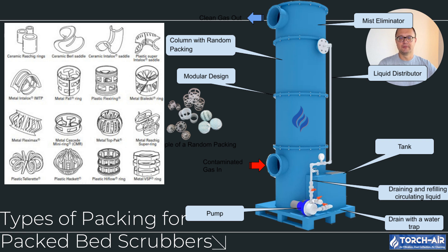Raschig rings: these are the OG of scrubber packing materials. Raschig rings are small, hollow cylinders that can be made from metal, plastic, or ceramic. They're great for low-pressure applications and are super durable in high temperature or corrosive environments. But while they provide decent surface area, there are more efficient options available today.